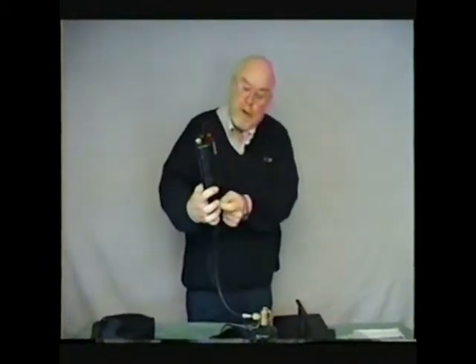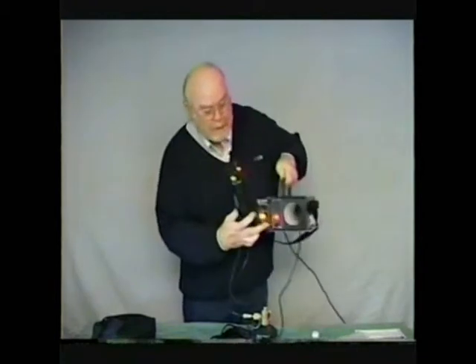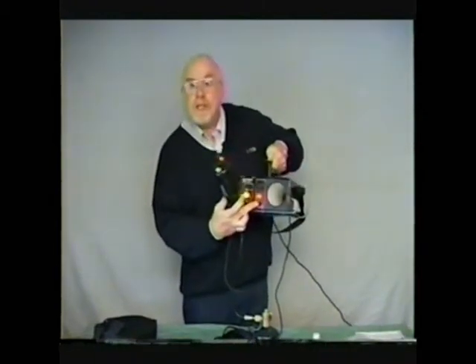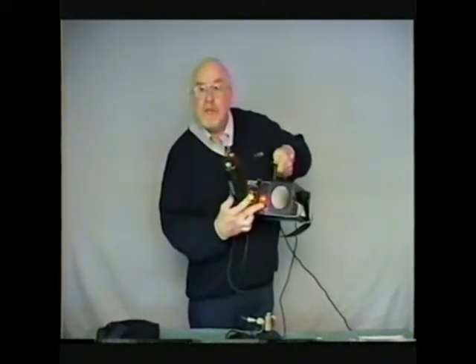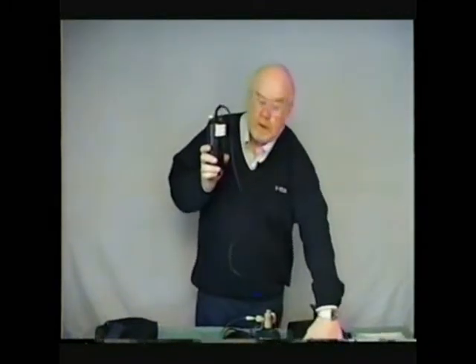Okay, I have a flow of gas waiting for my unit to alarm. I'm not going to release this testing hose just now, to show you that it is impossible to reset the unit while there is still a gas condition present. I'll remove the gas, disconnect my hose. You see that the red light went out, and now I can reset the unit.